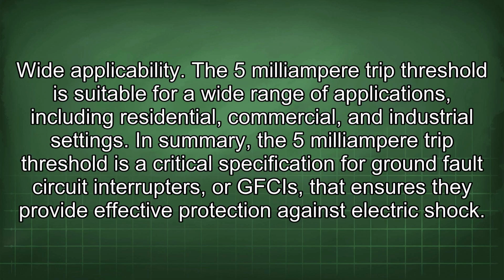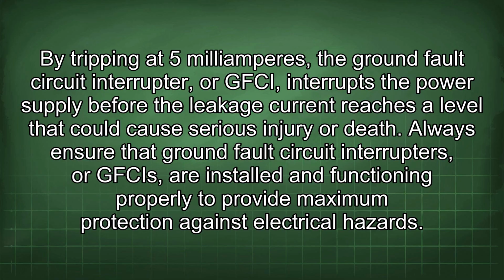The 5 mA trip threshold is suitable for a wide range of applications, including residential, commercial, and industrial settings. In summary, the 5 mA trip threshold is a critical specification for GFCIs that ensures they provide effective protection against electric shock. By tripping at 5 mA, the GFCI interrupts the power supply before the leakage current reaches a level that could cause serious injury or death.